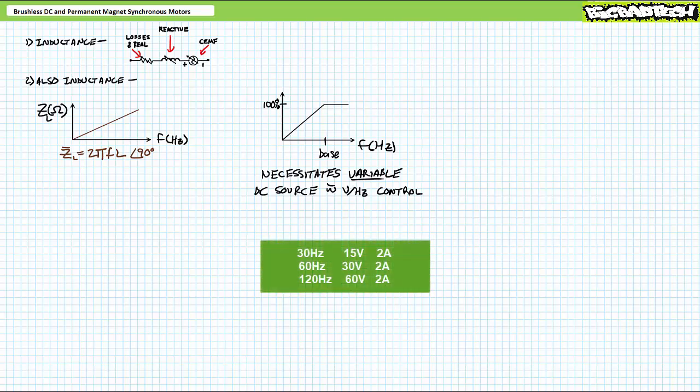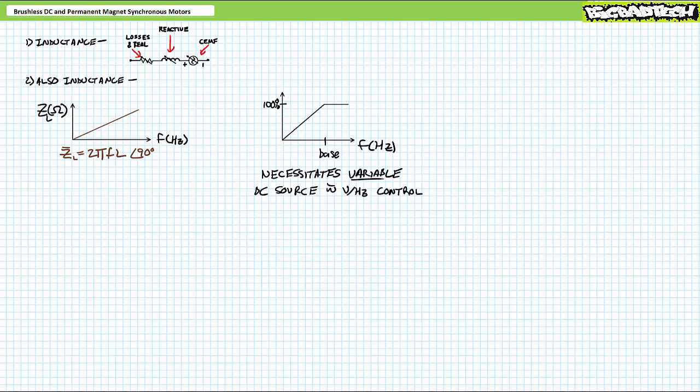For example, consider a brushless DC motor operating at a primary frequency of 30 hertz at 15 volts such that the stator windings draw 2 amps of current. At an increased excitation frequency of 60 hertz, the inductive impedance of the stator windings doubles such that at 30 volts the windings still draw only 2 amps of current. At an even higher excitation frequency of 120 hertz, the inductive impedance again doubles such that at 60 volts the stator windings still only draw 2 amps of current. Long story short, three-phase six-step 120-degree modulation can't use a fixed DC source if you want to keep current manageable, and must employ a variable voltage source using volts per hertz control.